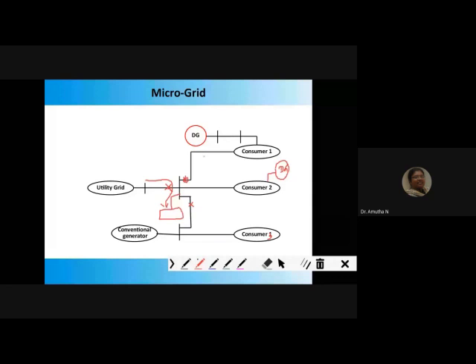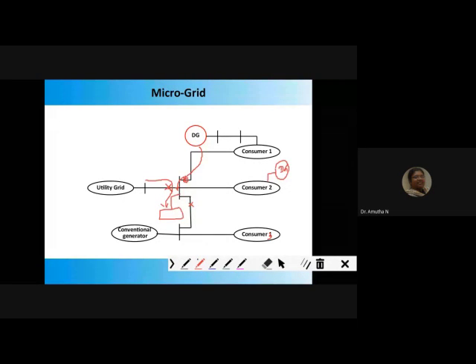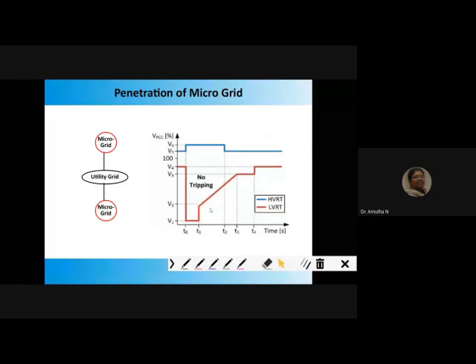It means that it is going to supply some power to this fault, because this DG is going to supply some fault current to the fault which is available at the grid side. So the DG is going to supply some fault current to this fault, right? That part we will call low voltage ride through or fault ride through.